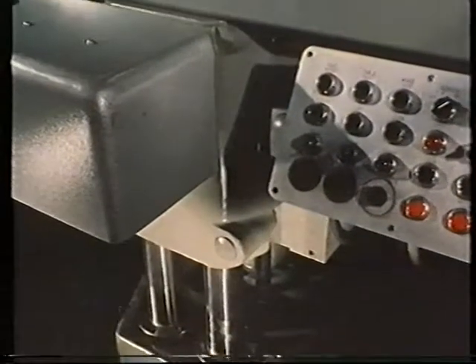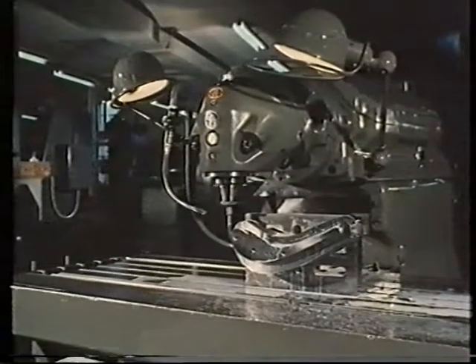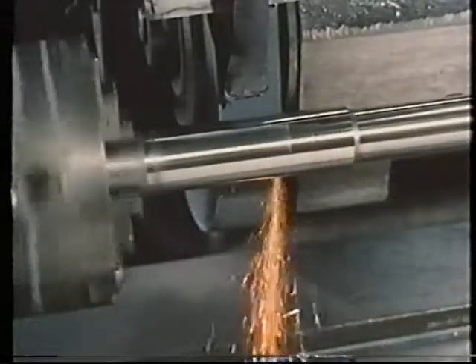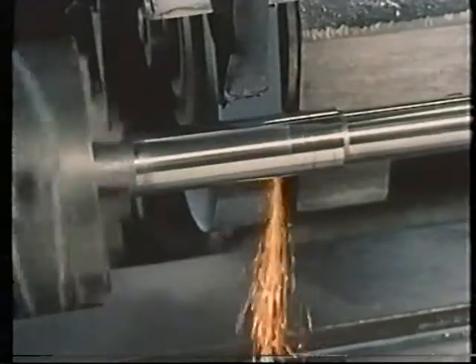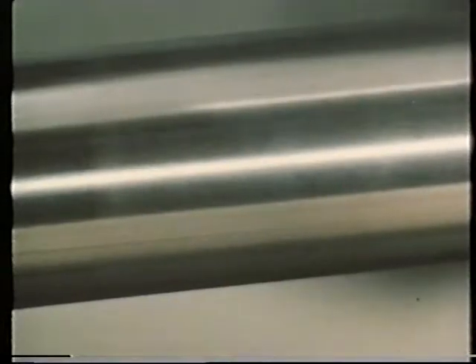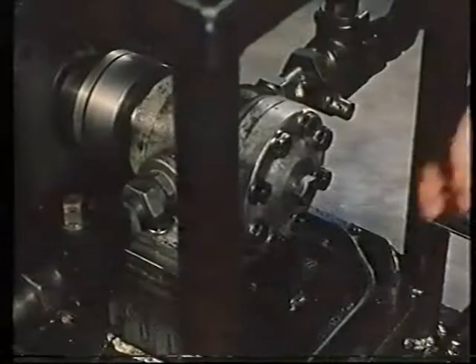Air must also be kept out of hydraulic systems. It is compressible and makes controls spongy. It has made the feed on this grinder unsteady, giving a poor surface finish. Air can be drawn into hydraulic systems through leaks in the suction side, and get compressed in the pump. The bubbles of compressed air heat up, and produce conditions suitable for rapid oxidation of the oil.